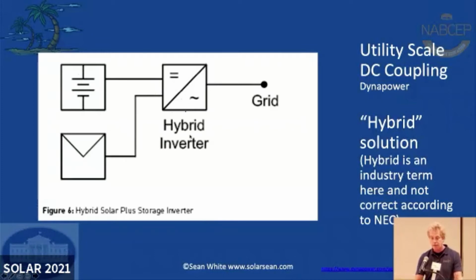According to the NEC, though, a hybrid system does not include batteries. It'll say a hybrid system means it's PV and wind or PV and a generator, but not batteries and not the grid. They exclude the batteries and the grid. So a hybrid inverter is not necessarily hybrid according to the NEC definition, but according to my friend Bill, they're probably taking that out in the 2023 National Electrical Code. Just remove the term hybrid from the NEC.